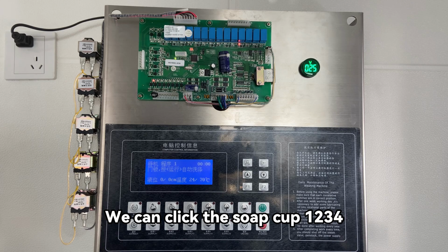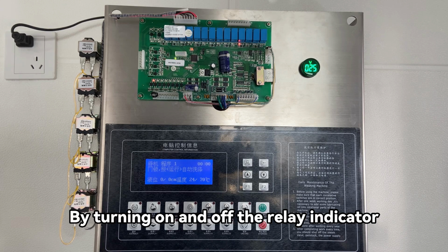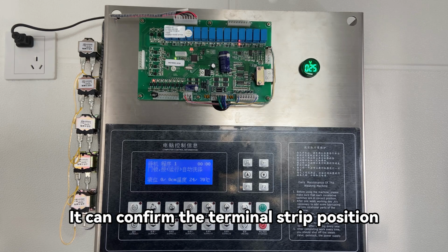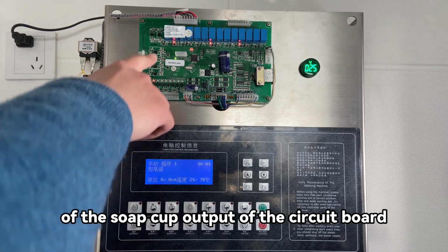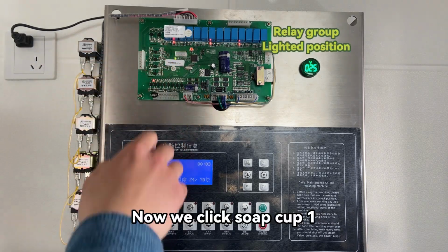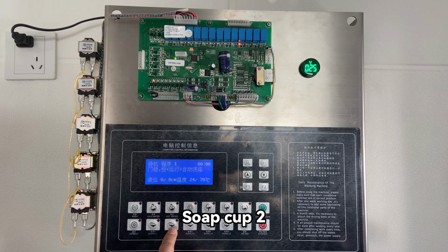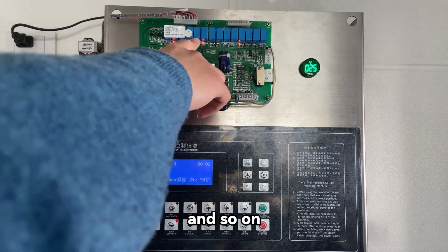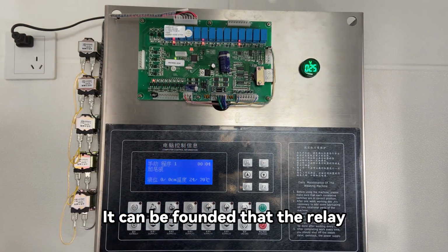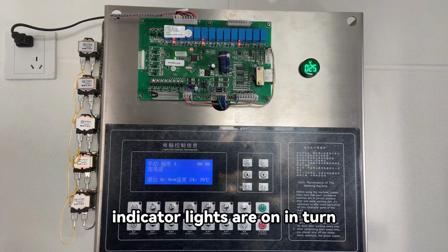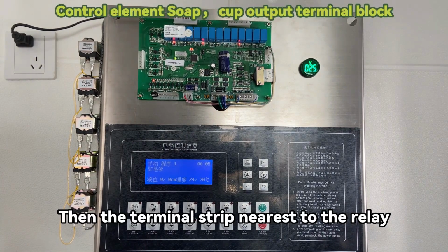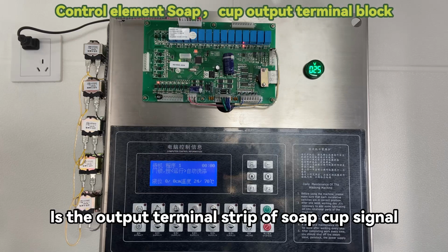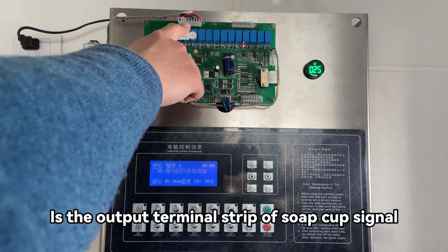We can click soap cup 1, 2, 3, 4 at the control panel by turning on and off the relay indicator on the circuit board. This confirms the terminal strip position of the soap cup output on the circuit board. Now we click soap cup 1, soap cup 2, and so on, and find that the relay indicator lights turn on in sequence. The terminal strip nearest to the relay is the output terminal strip of the soap cup signal.